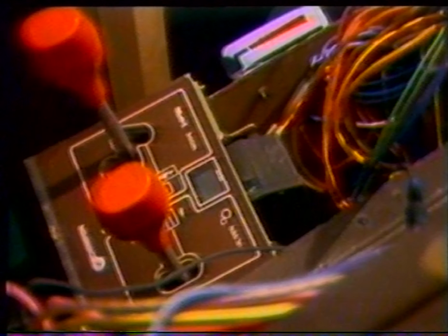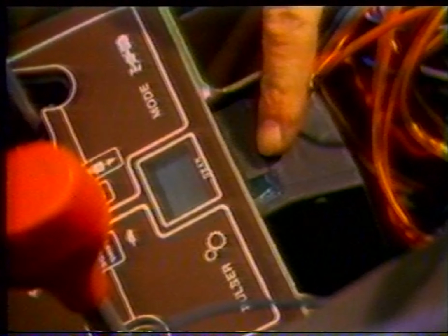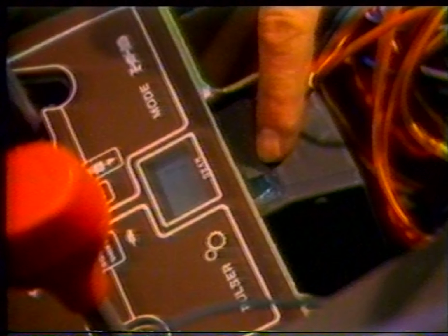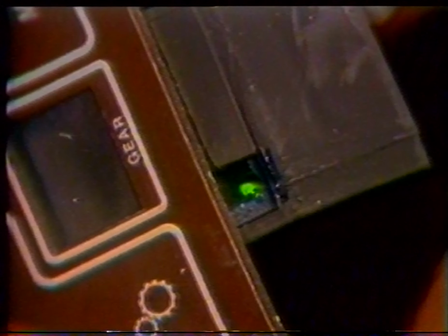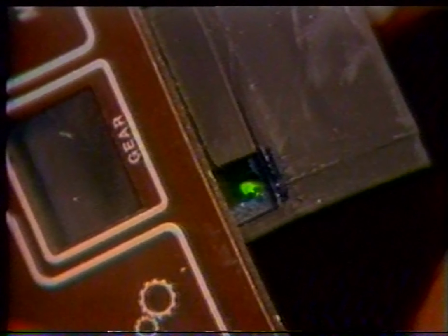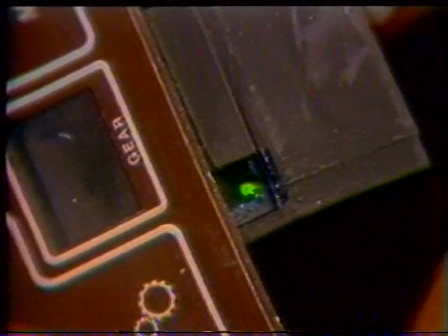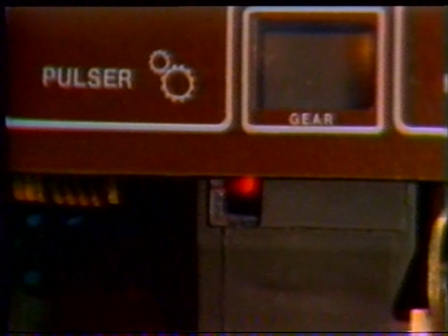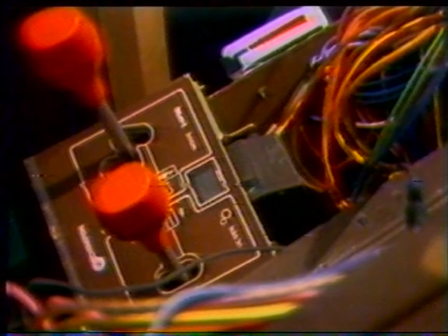If all circuit breakers are normal, remove the screws retaining the console and lift it up to expose the controller. With the key on, look directly behind and to the left of the LCD display for a green or red light. If the green LED is on, the controller is functioning properly. If the red light is on, the controller has malfunctioned and may have to be replaced. If no light is on, power to the controller is below 9 volts. Check the power supply and ground to the controller.